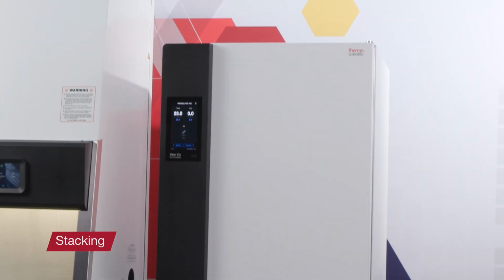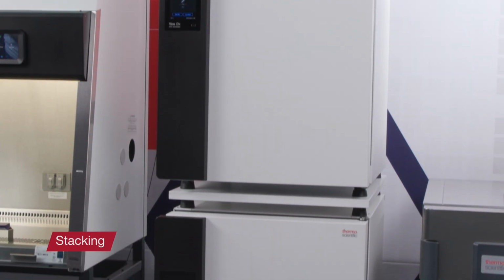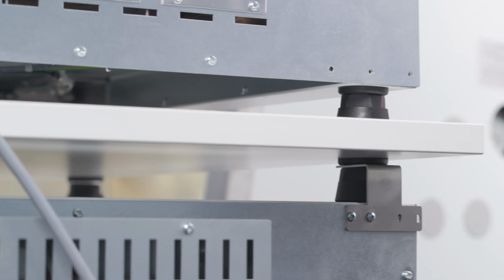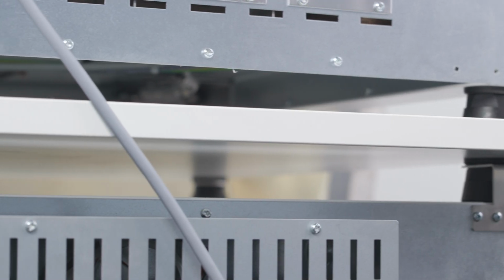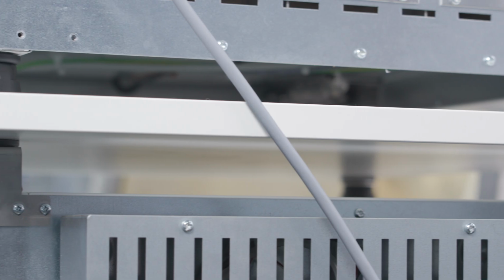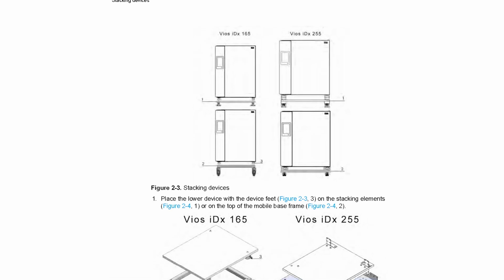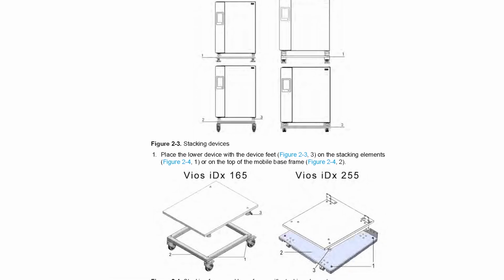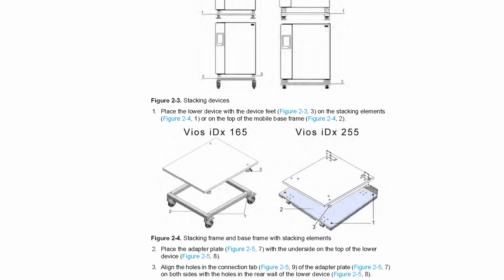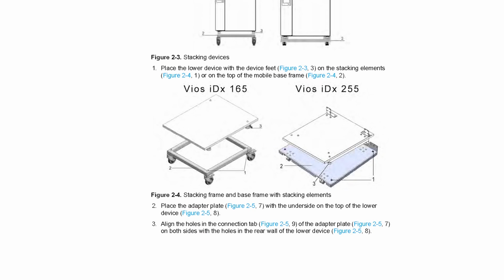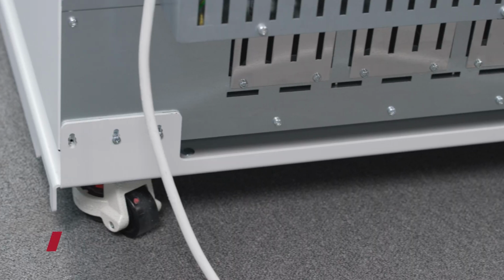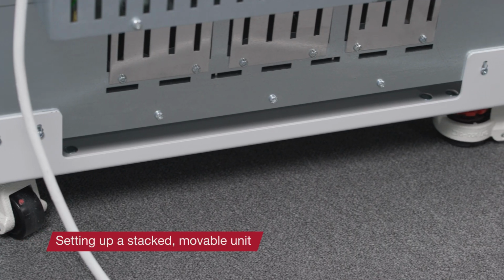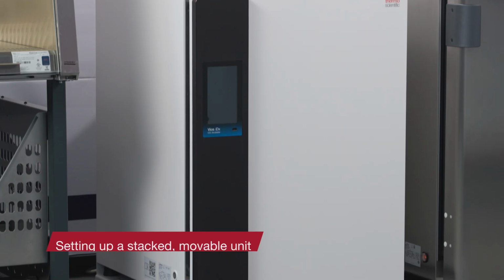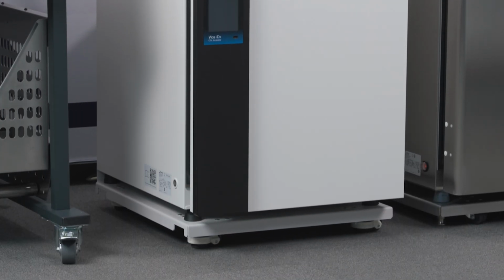You can save space by stacking a maximum of 2 CO2 incubators. You'll need to place an optional stacking adapter between the two units to create a stacked configuration. When installing the stacking adapter, refer to the Stacking Devices section of the Vios iDx CO2 Incubator operating instructions for details. A mobile base frame helps you move your incubator around your lab or facility. It can also be used to set up a stacked, movable unit.